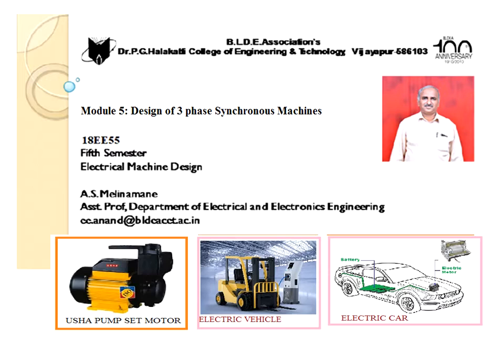To generate the AC voltage of 50 Hz, the machine has to run at only one speed, that is synchronous speed. Ns equals 120 f by P, as per the desired frequency and the number of poles. So it directly depends. The machine should always run at that speed, irrespective of loading action. So it is referred to as a synchronous machine.